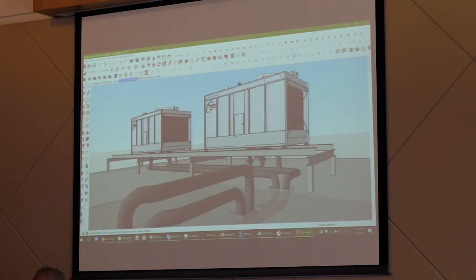So you could put a sensor up here to control the tower fans and have the sensor down there control the bypass. Is there any potential problems with that? There's two, basically. What are they? Failed sensors. Well, not even failed sensors. Okay, three.